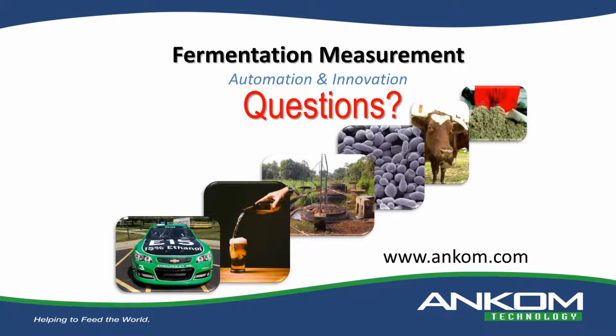Okay, the next question is, is there a specific reason that the system is permeable to CO2 to the point that the bottles can reach a negative pressure during a run? The only thing I can think of there is that somehow it's not sealed properly. In the manual, we do talk about CO2 permeation in the silicone that's used for the transducer. We actually made a lot of modifications to reduce that. So it is a very small amount of permeation of CO2 during a run. But as Greg said, if you're seeing significant amounts, then that's certainly going to be because there might be a pressure loss or something.